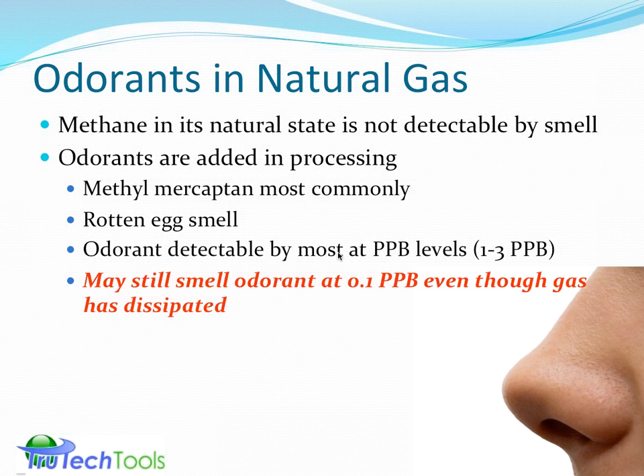So some of this commentary developed here came from some fire safety bulletins that are out there from some of the manufacturers and others in the fire safety industry, where they have to deal with these kinds of gas emergencies very often, the utility industry. So an odorant is not the be-all and end-all of gas detection. Don't assume or think that it's there as a public service, but it's not meant to rule out a meter that's used to detect.